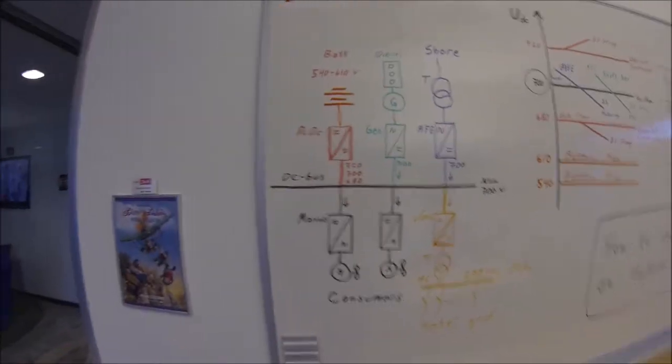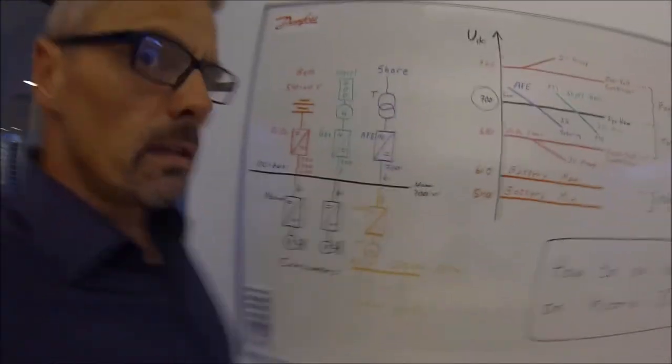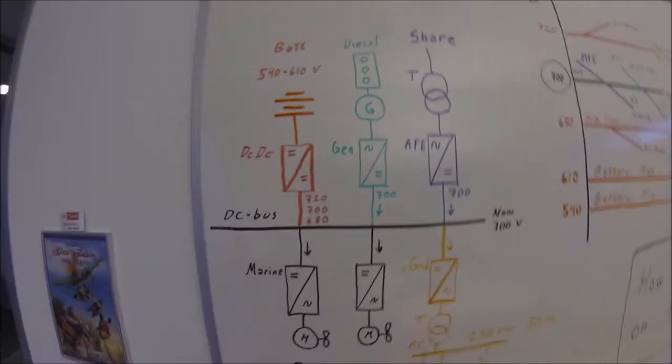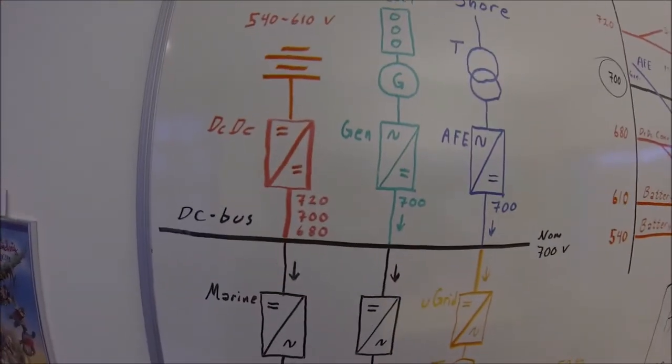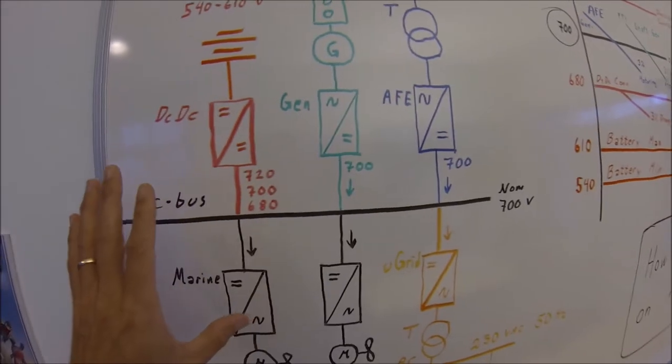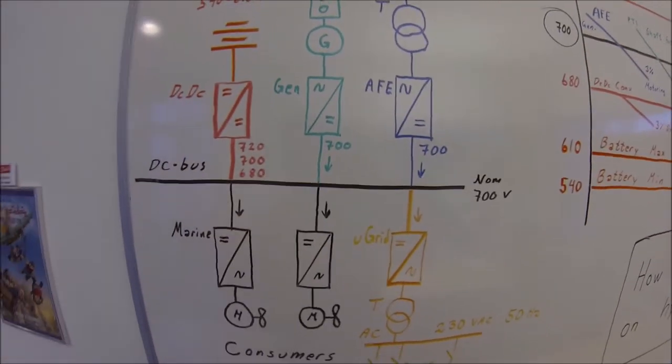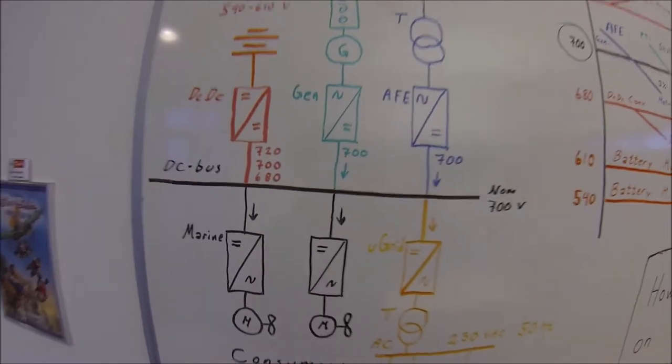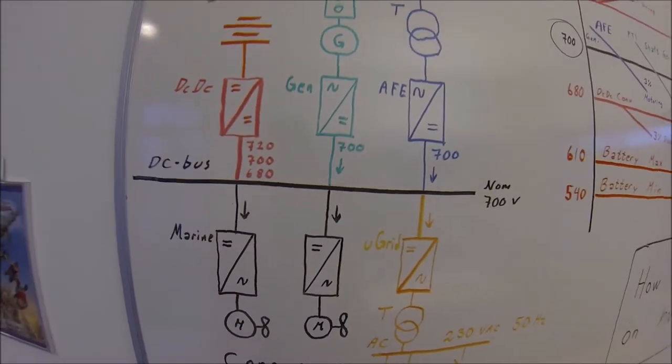So let the drive do it. Let the drive do what it is best at, and that is managing a DC bus. All of these applications have inbuilt control of the DC voltage. And it's just to put the settings and parameters so that it's synchronized and it will basically work on its own. And it's extremely fast.